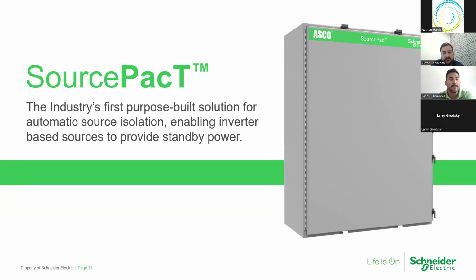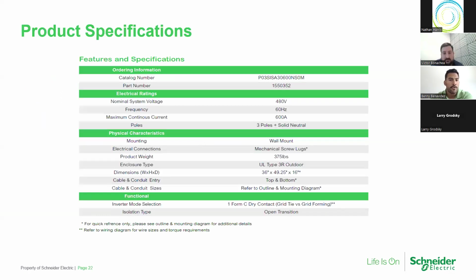We're compatible with them. SourcePacT is only an isolation switch with a very basic level microgrid controller to talk to the energy storage systems' inverters. So it's really vendor agnostic, and we're going to streamline this product out in the industry. For our initial launch, the product is available at 600 amps at 480 volts. That's the most common we see out in the industry, and within the energy storage systems, they'll have an output transformer to step up the voltage to 480, 60 hertz, 3 poles, solid neutral.